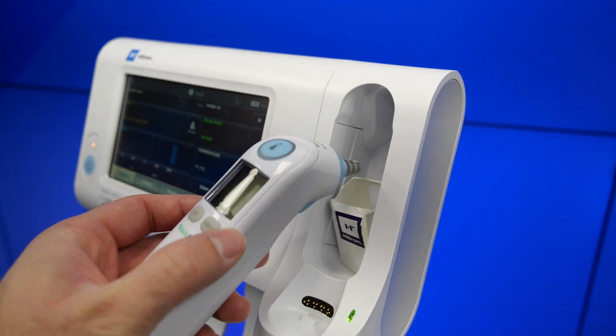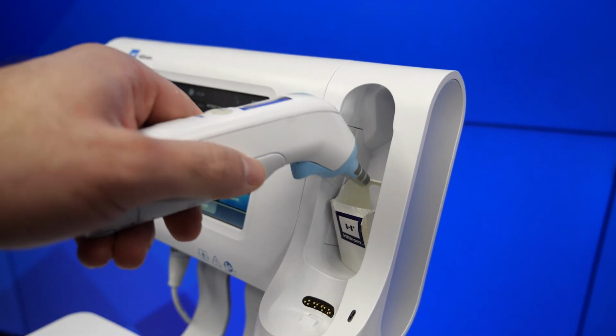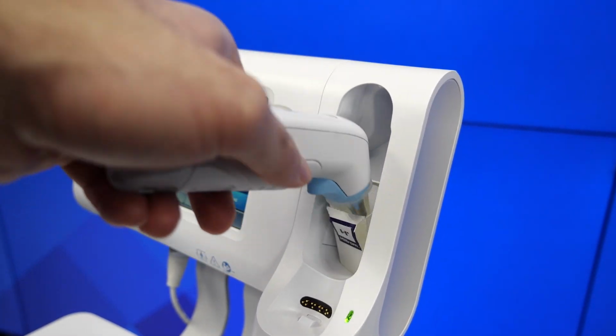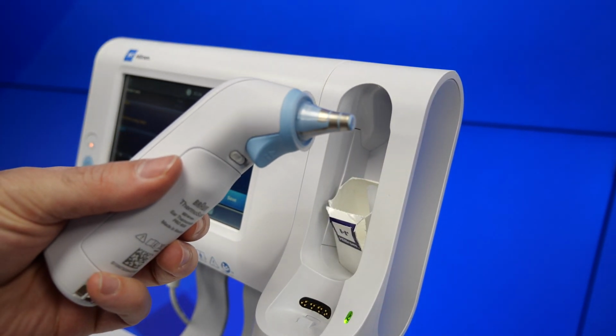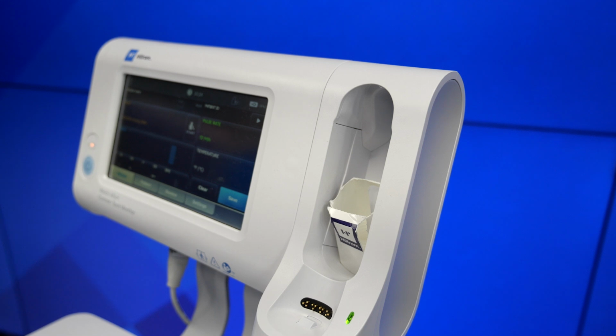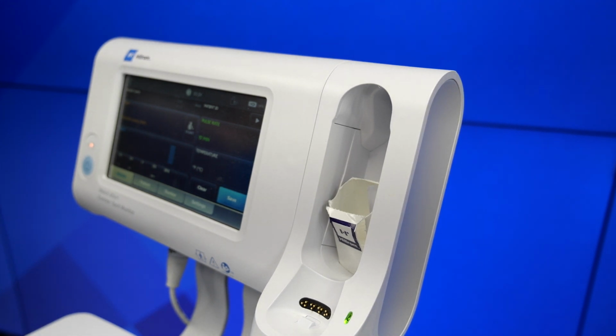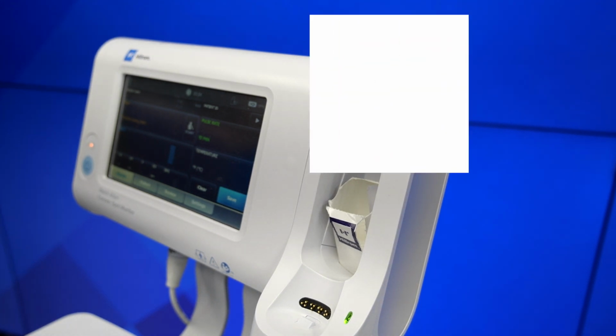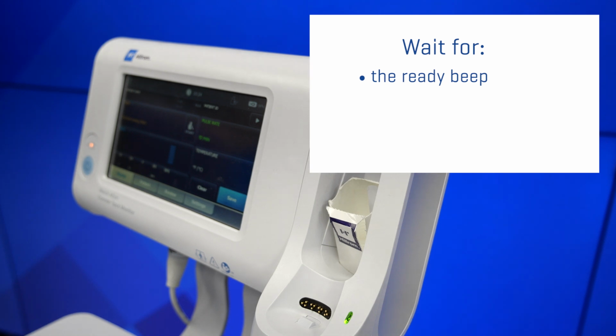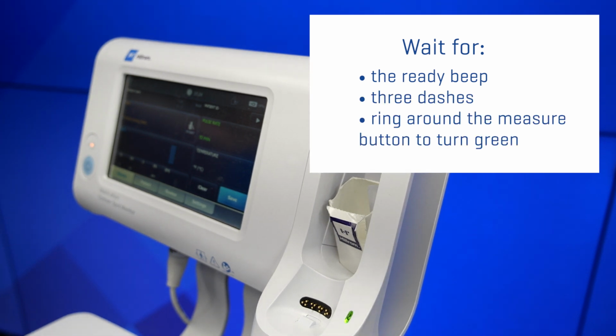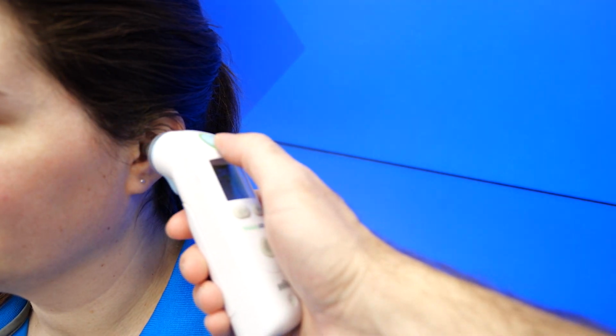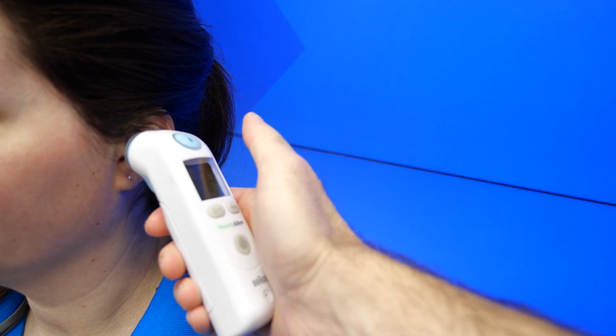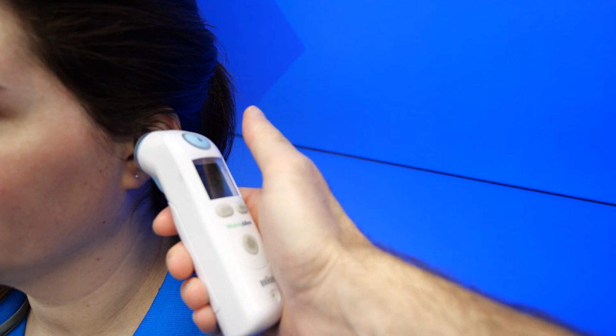temperature measurements. To take a measurement, begin by removing the ear thermometer from the dock. Locate the probe cover box. Firmly push the probe tip into the probe cover box. When the probe cover is in place, the thermometer turns on automatically. Wait for the ready beep, 3 dashes to appear on the thermometer display, and the ring around the measure button to turn green. Fit the probe snugly into the ear canal, and then push and release the measure button.